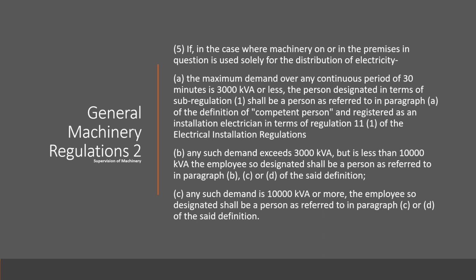If, in the case where machinery on or in the premises in question is used solely for the distribution of electricity, the maximum demand over any continuous period of 30 minutes is 3,000 kVA or less, the person designated in terms of Subregulation 1 shall be a person as referred to in paragraph A of the definition of competent person and registered as an installation electrician in terms of Regulation 11.1 of the Electrical Installation Regulations. If any such demand exceeds 3,000 kVA but is less than 10,000 kVA, the employee so designated shall be a person as referred to in paragraph B, C, or D of the said definition. If any such demand is 10,000 kVA or more, the employee so designated shall be a person as referred to in paragraph C or D of the said definition.